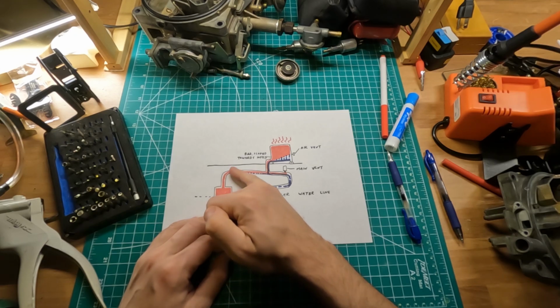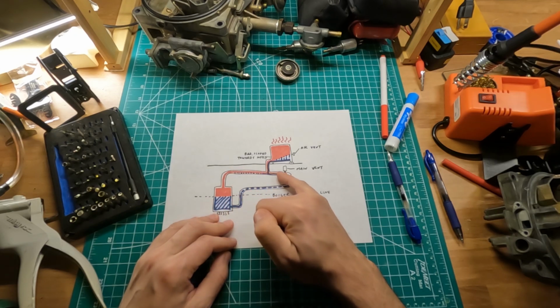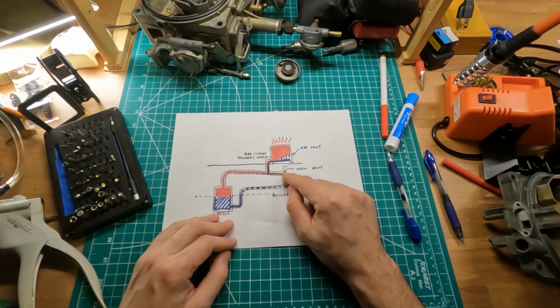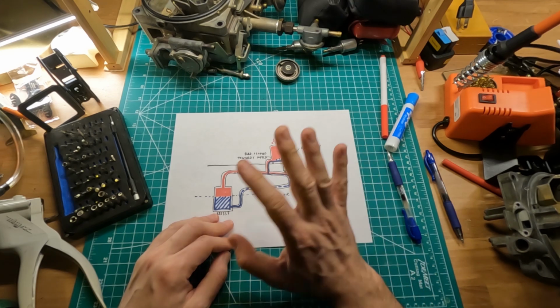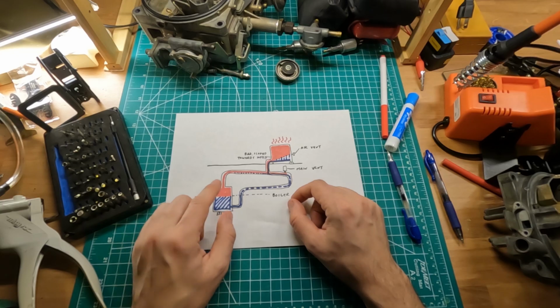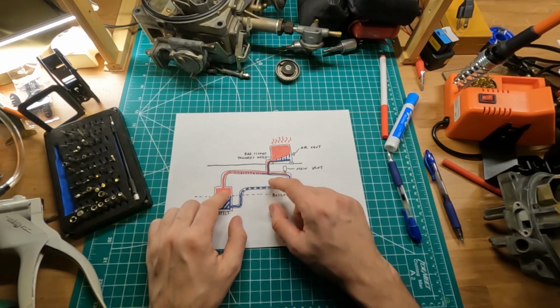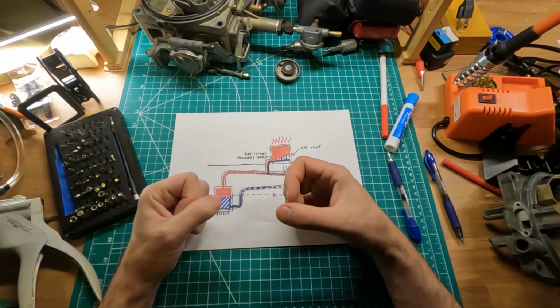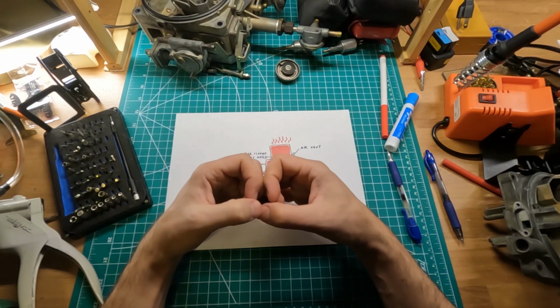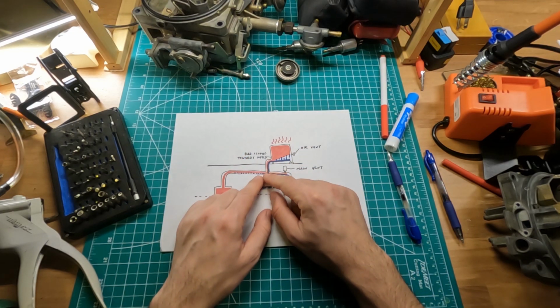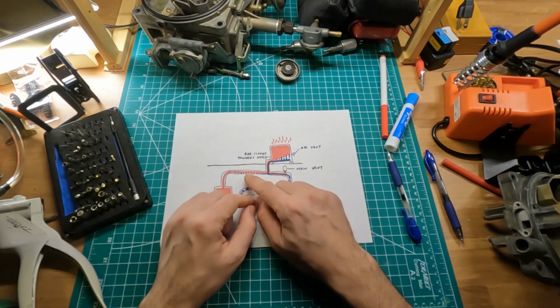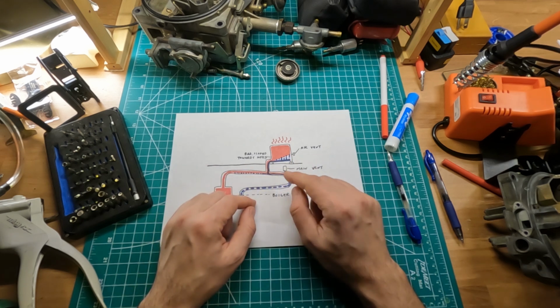Via the pipes, we send it down the main to this thing called the main vent. The main vent is basically an opening in the pipe. Now, why is it necessary? It's because steam and air don't mix. Those are two gases, and one is pushing on the other. At the same time, you cannot compress air. You have to release the air from the main pipes via something.